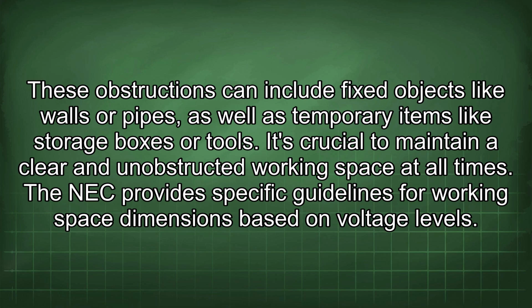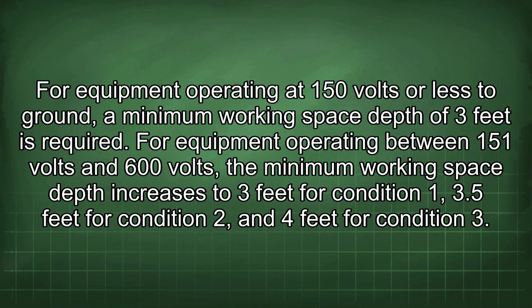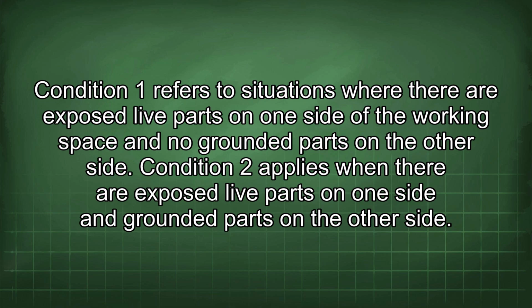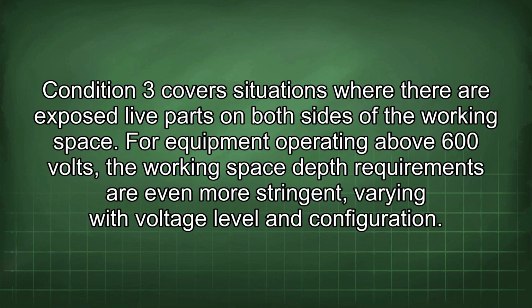The NEC provides specific guidelines for working space dimensions based on voltage levels. For equipment operating at 150 volts or less to ground, a minimum working space depth of 3 feet is required. For equipment operating between 151 volts and 600 volts, the minimum working space depth is 3 feet for condition 1, 3.5 feet for condition 2, and 4 feet for condition 3. Condition 1 refers to situations where there are exposed live parts on one side of the working space and no grounded parts on the other side. Condition 2 applies when there are exposed live parts on one side and grounded parts on the other side. Condition 3 covers situations where there are exposed live parts on both sides of the working space.